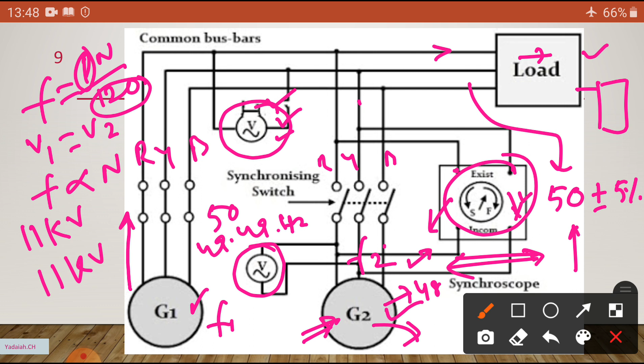Suppose the pointer moves in the other direction, that means the incoming machine's rotor is rotating slow. Then you have to increase the speed by watching the synchronoscope until it is vertical. That means it should not be slow, it should not be fast, it should be equal. Whatever the frequency of the incoming machine, if it equals the existing frequency, it indicates vertical.